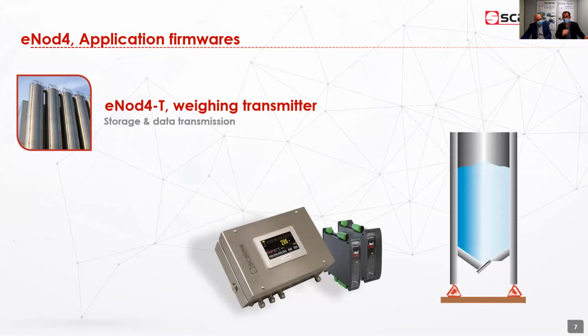So at first, let's start with the eNod4T, which is the basic model, if I can say, because this is a transmitter, converting the millivolt signal from a strain gauge load cell into a digital signal, because it integrates an A to D conversion mode.